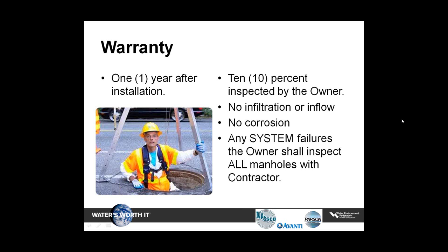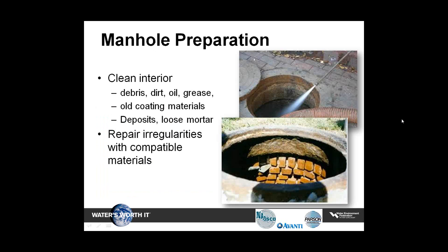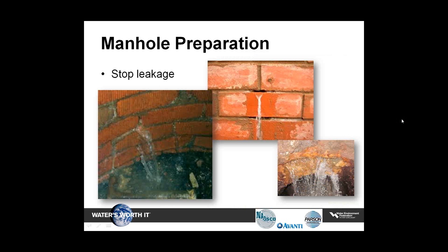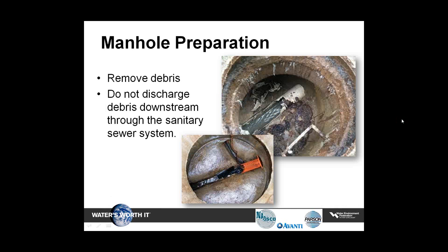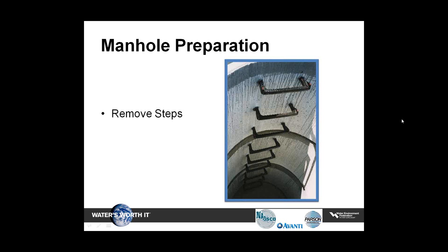Preparation of the manhole must include cleaning the interior surfaces to eliminate debris, dirt, oil, grease, and remains of old coatings. Remove loose mortar and concrete. Pressure washing levels used for cleaning shall be as recommended by the manufacturer. Repair irregularities in the manhole. Repair leakage using compatible materials that are compatible with the proposed resurfacing material. Trim grout at incoming landings and pipes as required. Remove debris from manhole and incoming sewer connections. Properly dispose of debris and residue from cleaning. Remove the steps flush.